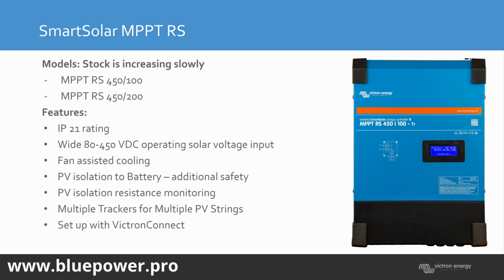One thing to note is if you're installing them in a very high moisture area, it is recommended to put petroleum jelly or any anti-flashing material or terminal paste onto the PV terminals. Because of installations in high humidity, it has caused flashover on the PV terminals at high voltages. So the installers just put petroleum jelly over the terminals. But yeah, if you've got it properly connected and stripped, chances aren't that high, but in very high humidity areas, it is a chance. But that's above 90%, I would say. So just maybe install it in an enclosed area, not something that's open to the outside air here by the coast.